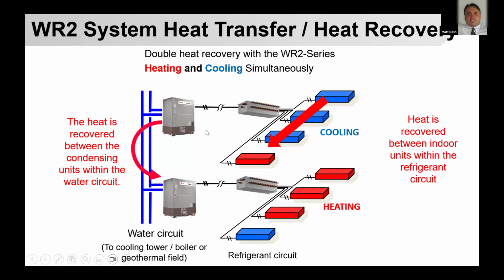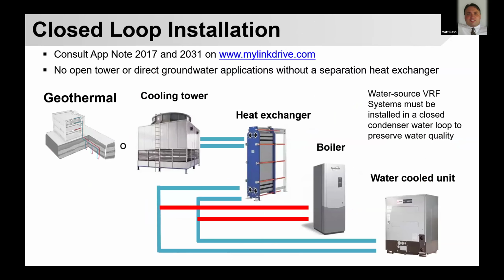So this is really kind of the best of both worlds. You've got optimized heat recovery on the refrigerant side, and then secondarily on the condenser water side. Because you're dealing with larger modules and they're serving multiple zones versus individual zoned water source heat pump systems, you'll often find with these systems, especially in the shoulder seasons, that your total peak compressor energy is reduced because these modules work to meet the dominant load, not the sum of the peaks. So that's one advantage that you have with this, and that can kind of optimize that geothermal design.